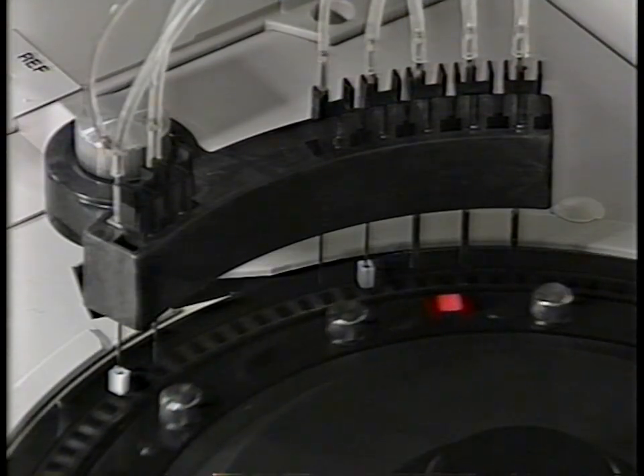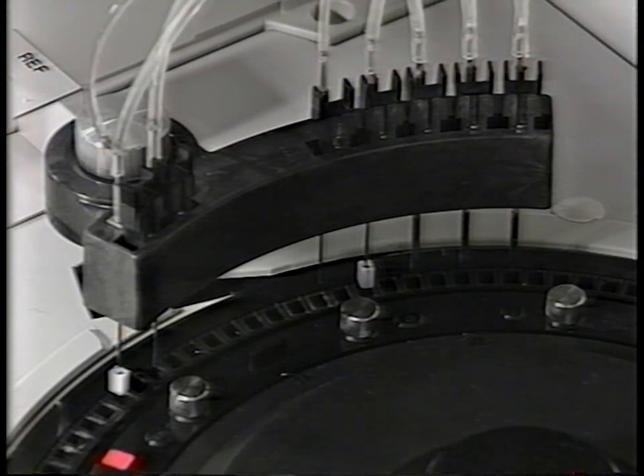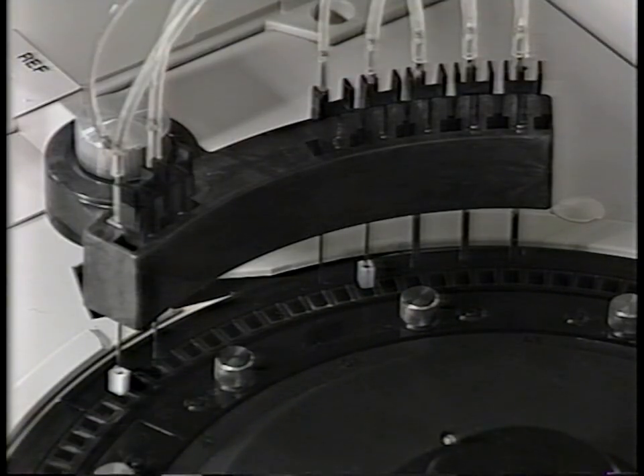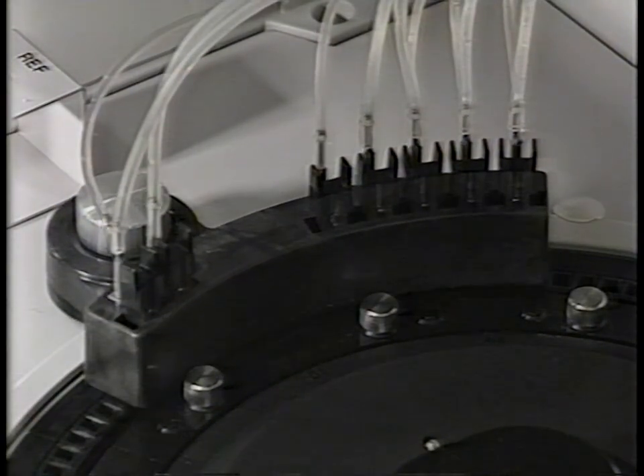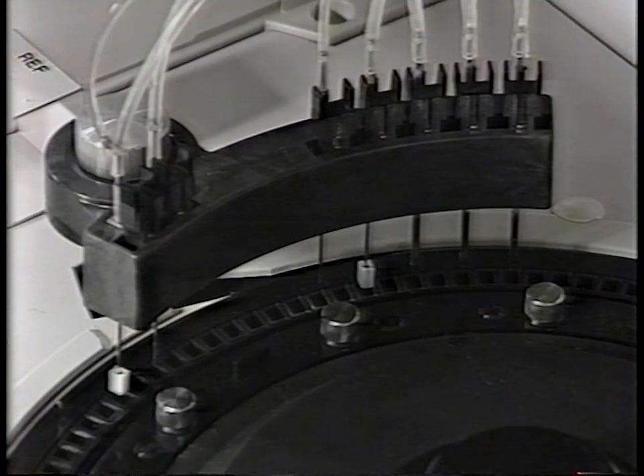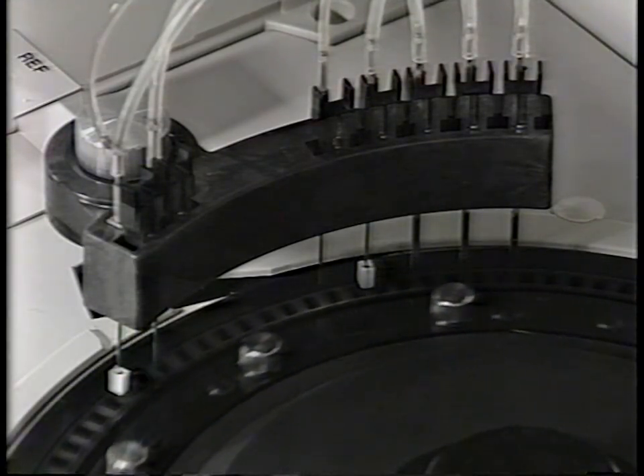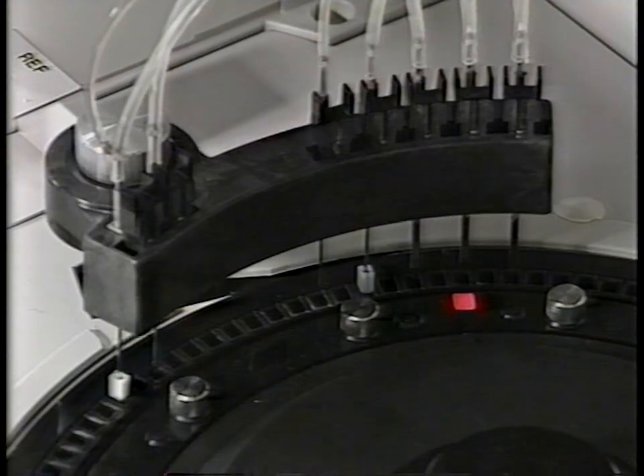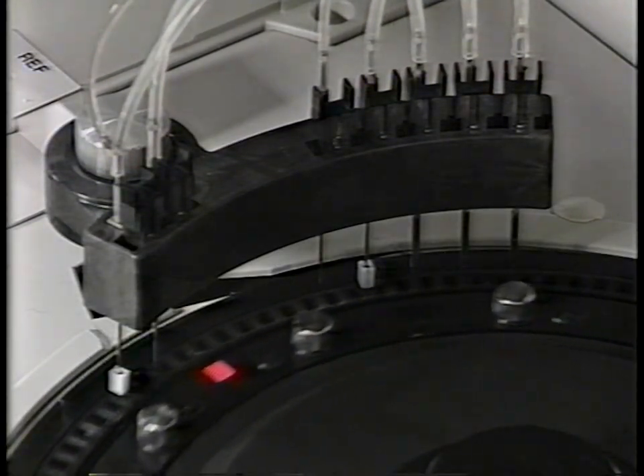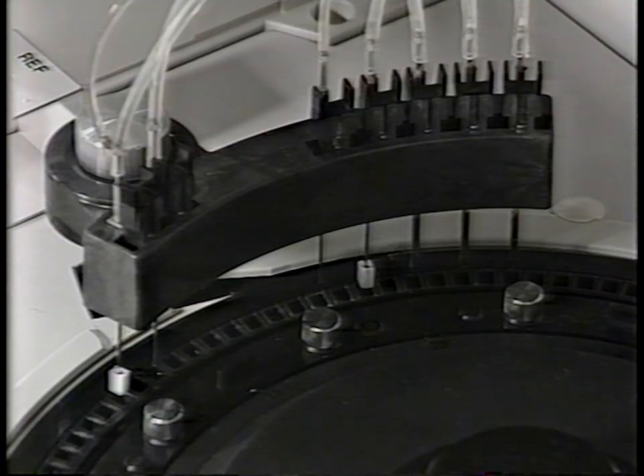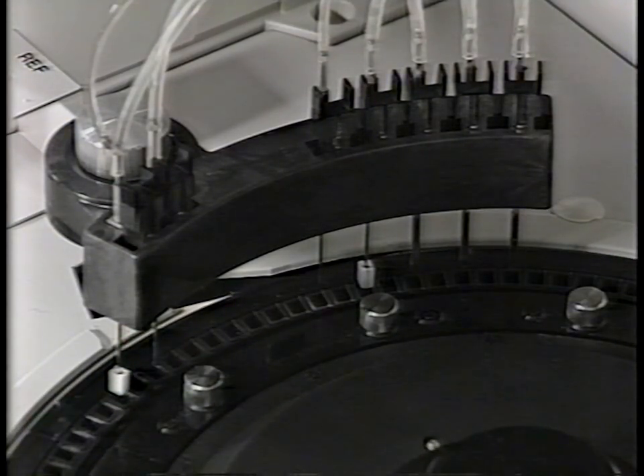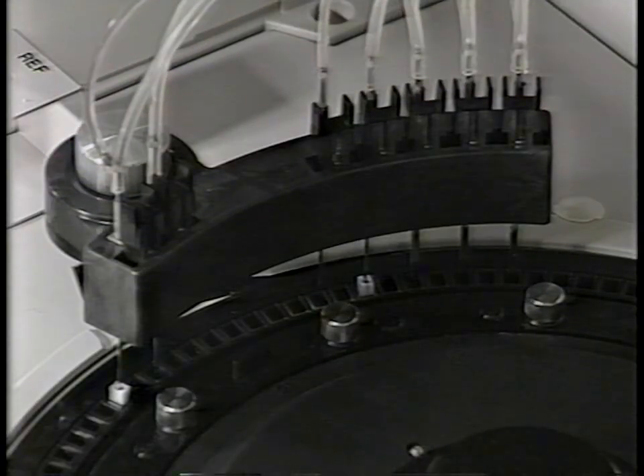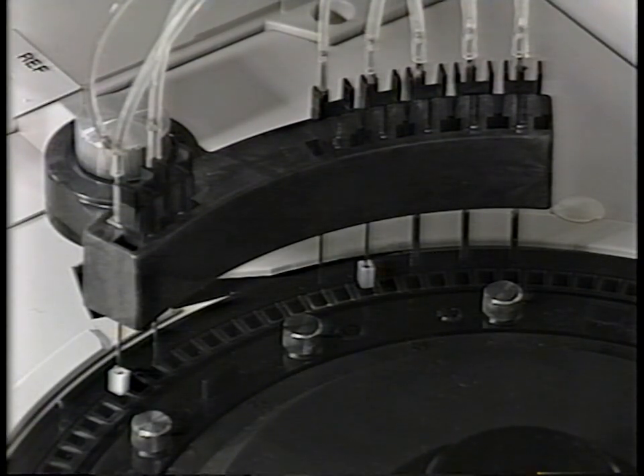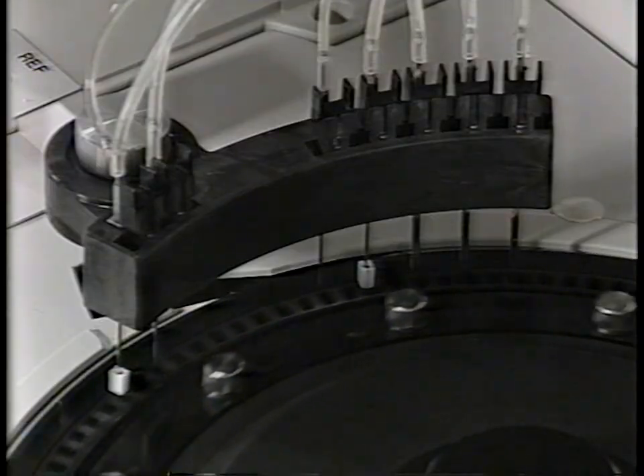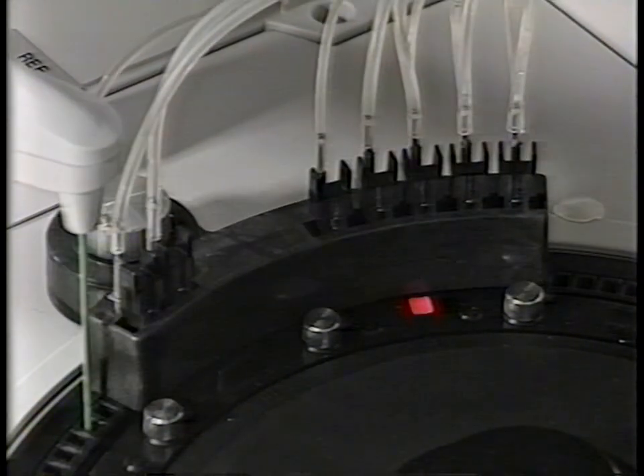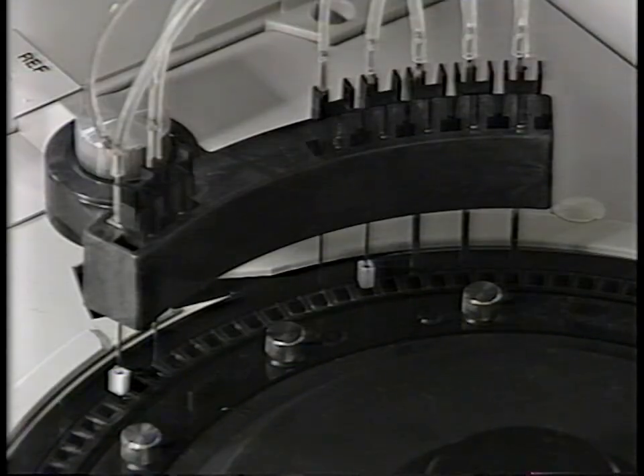After each reaction in a cell is measured for the final time, the reaction cell rinse mechanism cleans the cell. This occurs while the reaction disc is processing other cells. Cell Clean 90, a cleaning solution, is dispensed into the cell. After one rotation of the disc, the Cell Clean 90 is aspirated from the cell, and the cell is then rinsed with warm deionized water. This rinsing occurs over several rotations. Then, during the final stages of this process, the cell's optical integrity is checked and the cell is water blanked. Finally, it is dried before the next sample is dispensed into it.